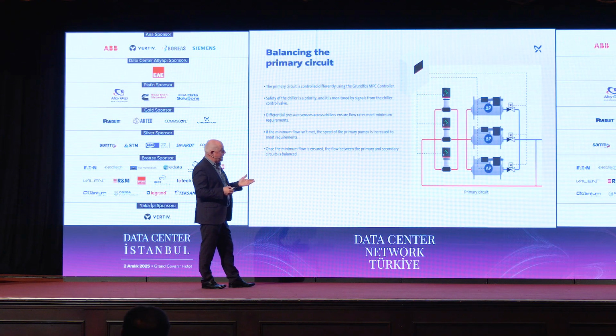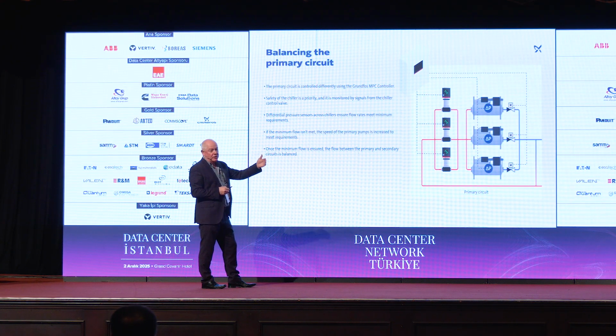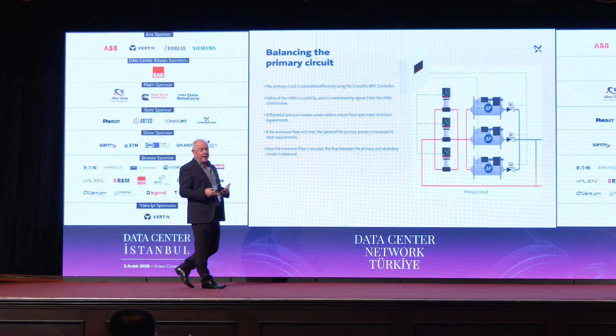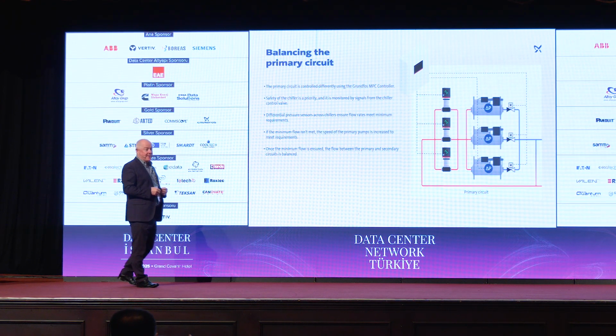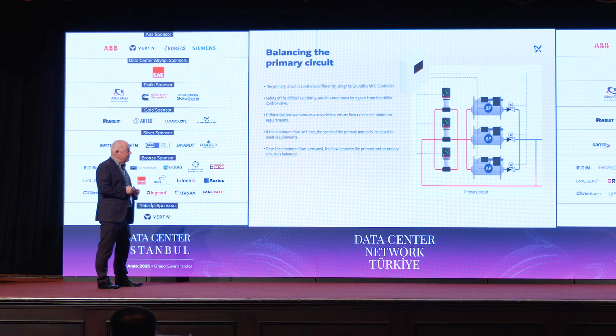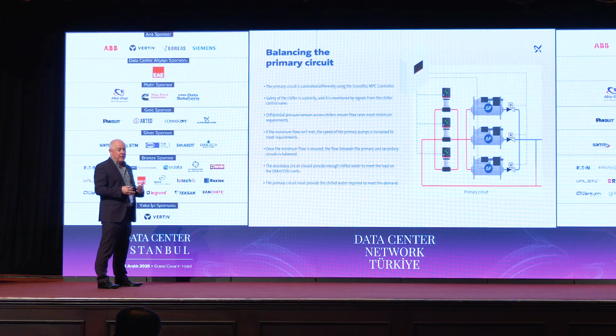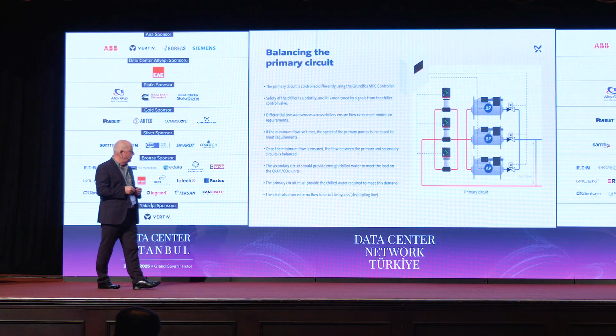Once that minimum flow is met, we start looking at what's going on the secondary side, and we speed up and slow down the primary pumps to meet the demand on the secondary side. And this gives us a very, very balanced system. And as I said, we're doing this in real time. It's constantly going on. We're constantly looking at the minimum flow to make sure we've got that, and then meeting the flow that's happening on the secondary side.